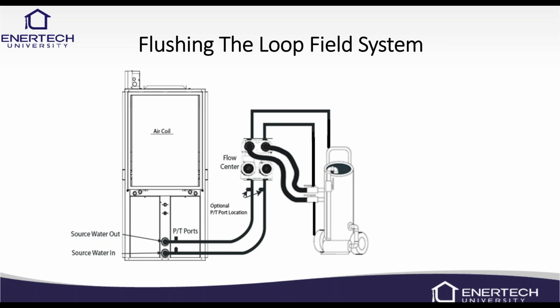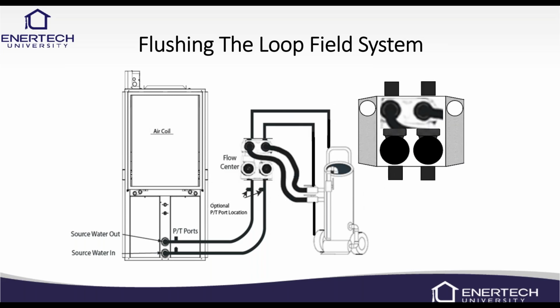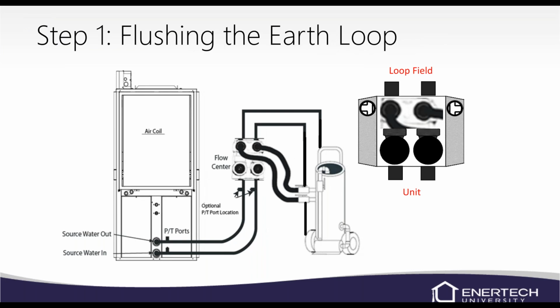So, flushing a loop field. This is a pressurized flow center. The three-way valves on the flow center. We want to start by flushing the loop field first. So we're going to basically turn our three-way valves to isolate the unit from the loop field, and we're just going to run the water through and flush through the circuit.